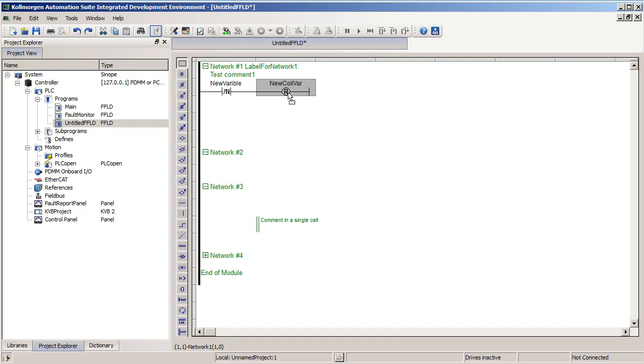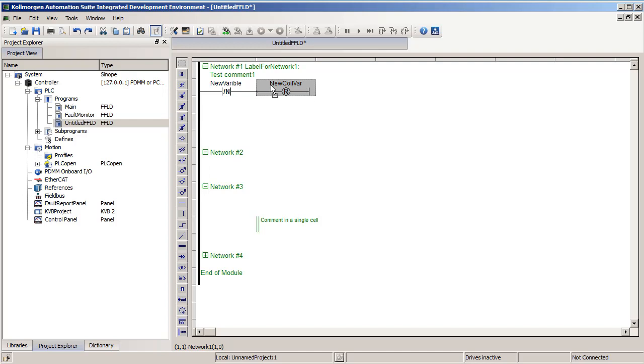We have a reset coil. When power is flowing to it, it will reset or make the variable false. But if power is not flowing to it, nothing will happen. Meaning a reset coil can only make the variable false. It cannot make it true.